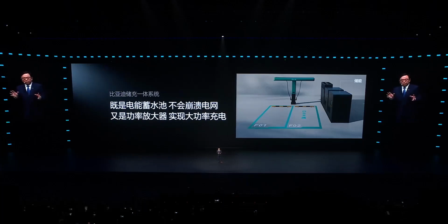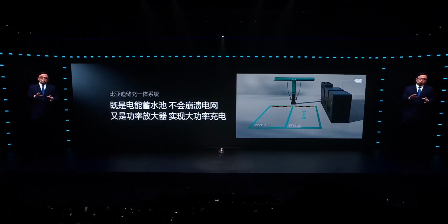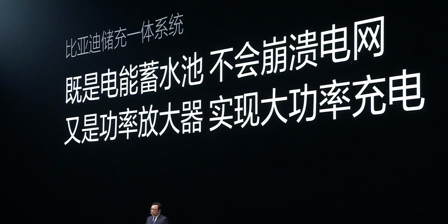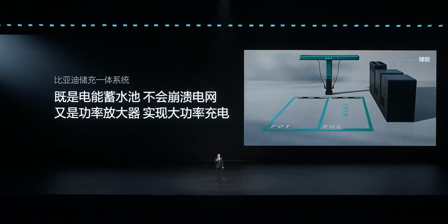Even if there is only one standard charging station with only 100 kilowatts, we use the same route. No additional copper wire or transformer required, no additional grid capacity needed, not even a kilowatt increase. After adding this energy storage system, it can turn a 100 kilowatt ordinary fast charging station's power instantly amplified 10 times, straight to 1 megawatt, instantly transforming into a fast charging station, breaking through the limitations of power grid capacity, and it will absolutely not damage the power grid.